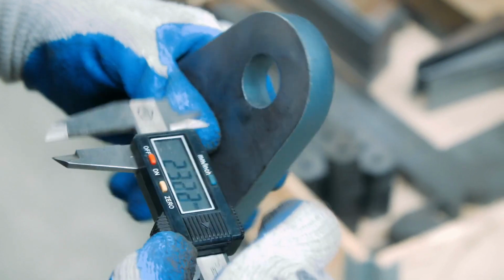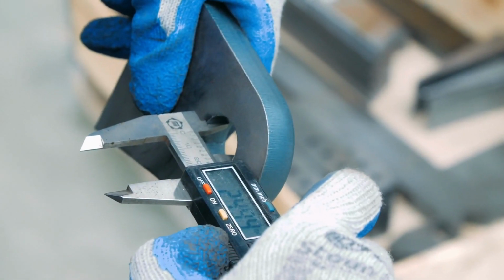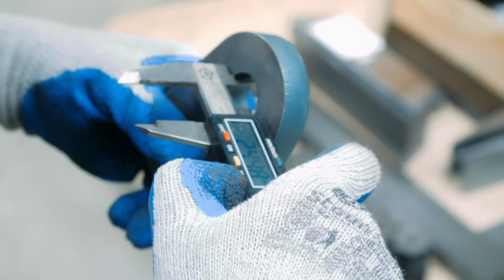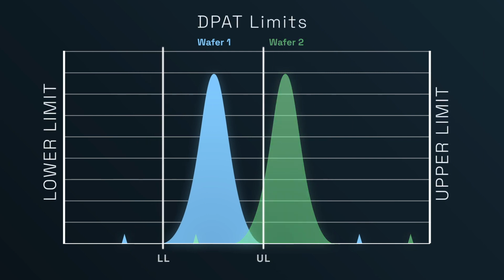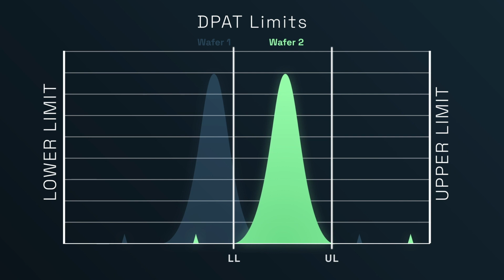Now, however, many industries use gauge studies, and many of the measurements taken don't have any spec limits. In those cases, R&R % is the gold standard. However, in the product and test engineering world, we have test limits for the parameters we're measuring, and we can use this as an advantage in gauge studies to reduce chasing our tails, debugging time, and getting to market faster.